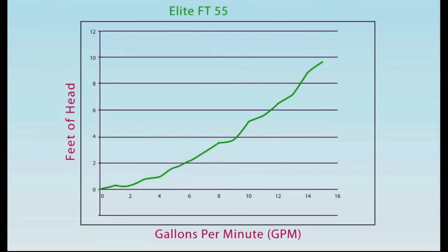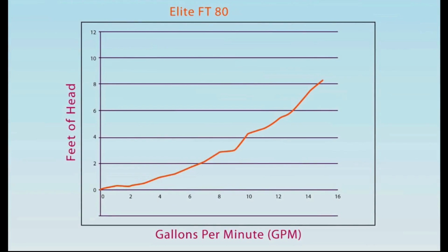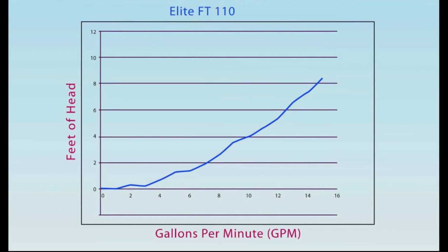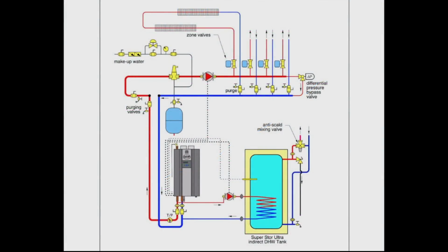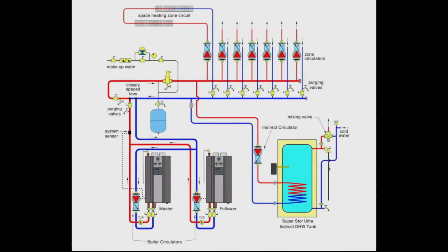The Elite Fire Tube Heater has a buffer of water in its design, which lowers the pressure drop through the heat exchanger and provides easy installation without the expensive primary and secondary piping methods that most traditional high-efficiency boilers require. Piping to the indirect is easy, and additional boiler line voltage outputs can be connected to the field connection board outputs to control the operation of either the central heating pump or the indirect pump for providing domestic hot water. Multiple boilers can also be piped together to provide system redundancy and a greater turndown for large commercial installations.